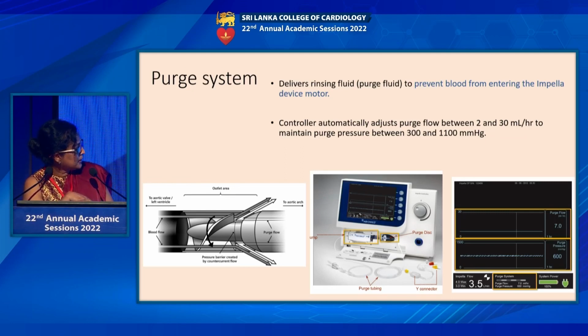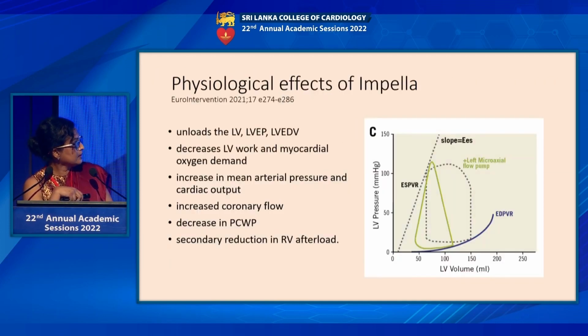Blood is coming from here, and the purge system will continuously purge fluid—heparinized fluid, D5—from this end, protecting the motor. That control is done by the machine, not by us, and it can go up to high pressures, the purging fluid.